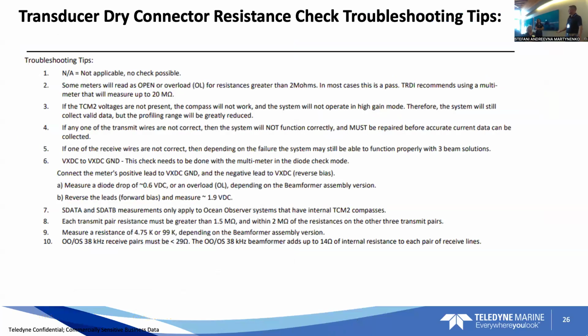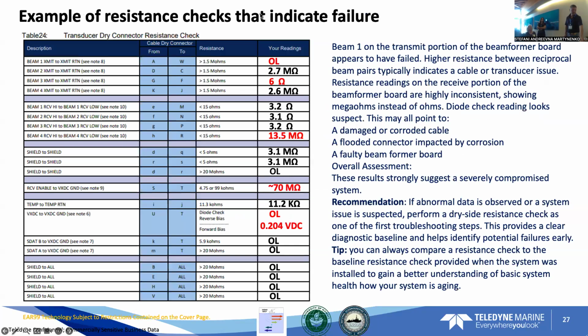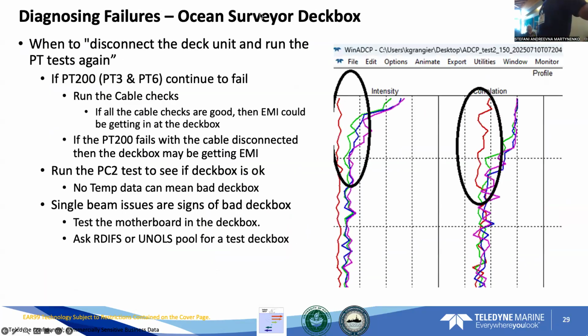For correlation, you're looking at the data. That's one of the 2 things you're looking at. Where is that slide? Here. So we use intensity and correlation. Intensity is the strength of the return. The correlation is, say you have 4 pings going out and you want 4 pings coming back, and you have to look at, well, do they line right up and how clean are they? That would be the simplest version of correlation I can come up with. And so that's data side, not really instrument level. But then it's the ceramics, and those are not field replaceable.